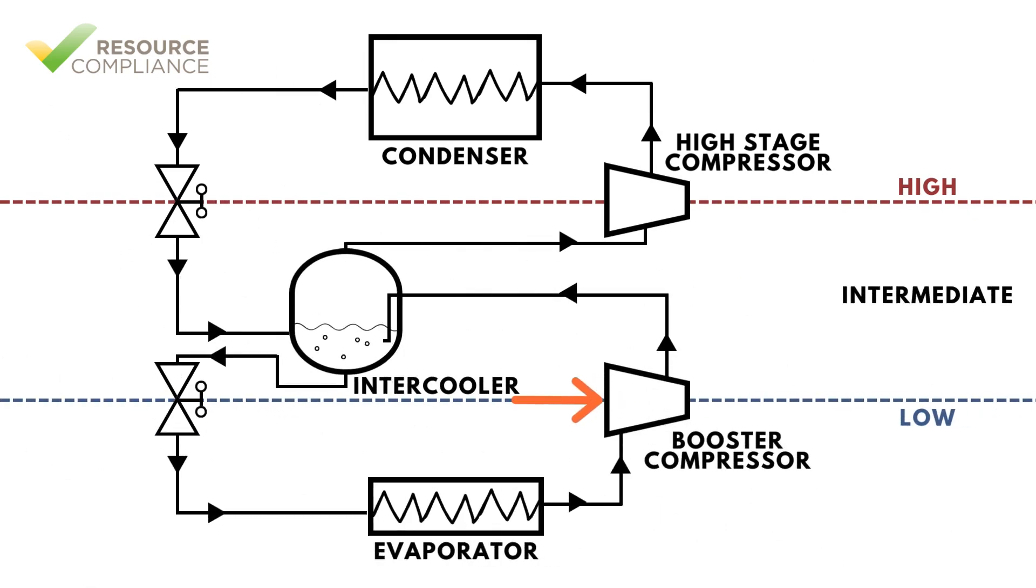The first stage compressor is called the booster compressor. Vapor from the evaporator is drawn into the booster compressor, where it is compressed to an intermediate pressure between the evaporator and condensing pressure.